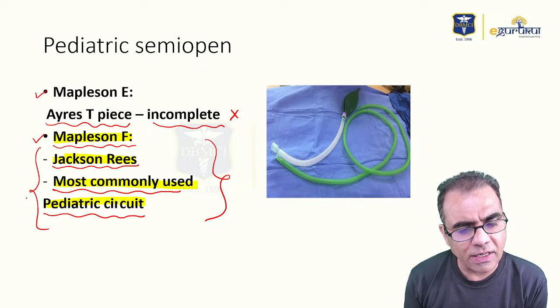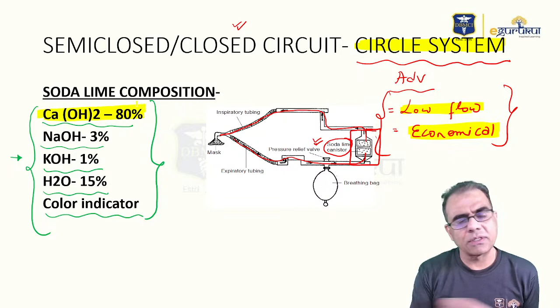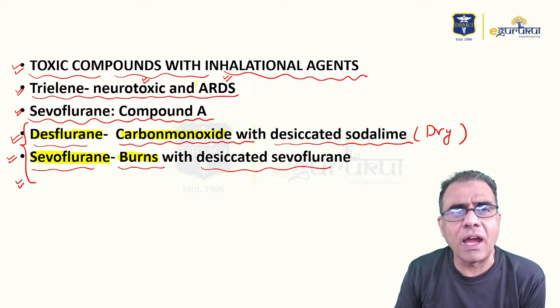Closed circuit or semi-closed circuit, which are also called the circle system, are preferred because they need very low flow and that makes them very economical. So definitely they are preferred over semi-open circuits. The major component of soda lime is calcium hydroxide, 80%. Some inhalation agents can react with soda lime to produce toxic compounds. The classical example was trilene, which could have caused neurotoxicity or ARDS, but I told you it's a matter of the past.